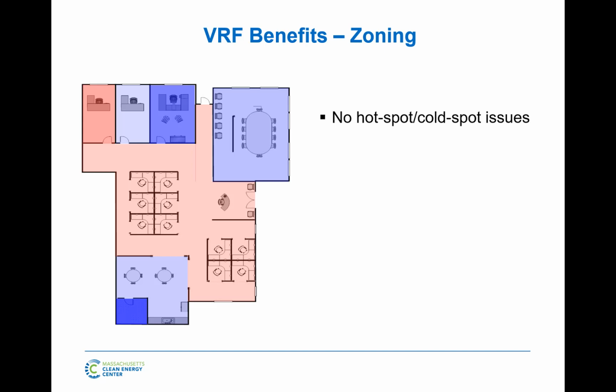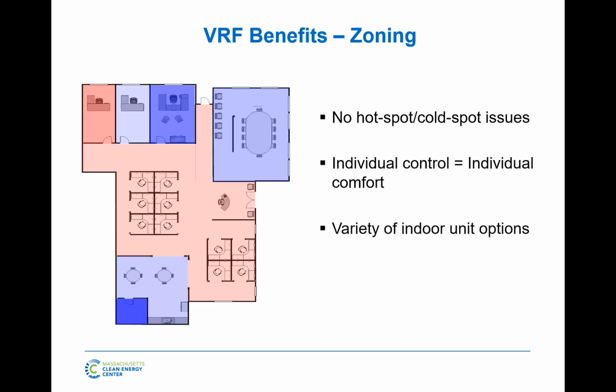Now, one thing to remember, VRF is a zoning system. If somebody comes to me and says, I have a big warehouse, it's 10,000 square feet, and it's all open, I want to do VRF, we're going to go, ooh, it might not be your best bang for your buck. Because VRF is all about multiple smaller units, they can go up to 8 tons, which is pretty big, but usually smaller fan coils that go in and zone your building. A building like this that we're in is a zone building. This is a bigger one. I might have 2 units in this room, but I might have offices upstairs, all different zones. That's where it makes sense.